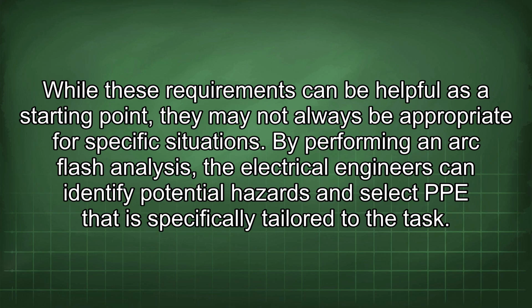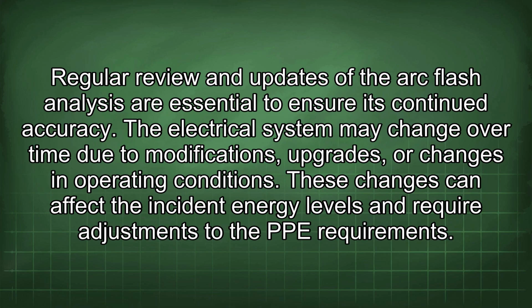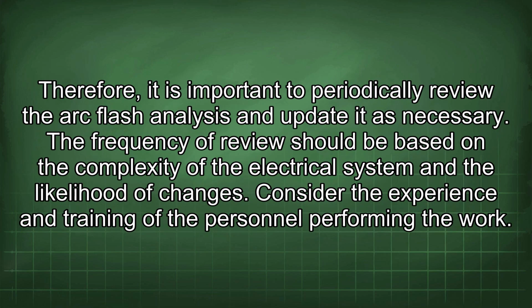Regular review and updates of the arc flash analysis are essential to ensure its continued accuracy. The electrical system may change over time due to modifications, upgrades, or changes in operating conditions. These changes can affect the incident energy levels and require adjustments to the PPE requirements. Therefore, it is important to periodically review the arc flash analysis and update it as necessary. The frequency of review should be based on the complexity of the electrical system and the likelihood of changes.